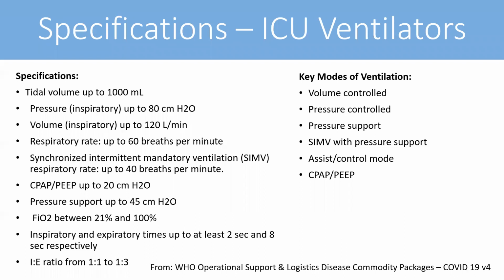So this is the specification of an ICU ventilator. Always remember you need to know about tidal volume, the inspiratory pressure, the inspiratory volume of the line. Respiratory rate is very important, and CPAP and PEEP are very important as well. So this specification is very important, and so are the key modes of the ventilator. Earlier I did explain about volume control modes and the types of modes that you're going to see. So it's very important that when you get an ICU ventilator, it has these types of modes.